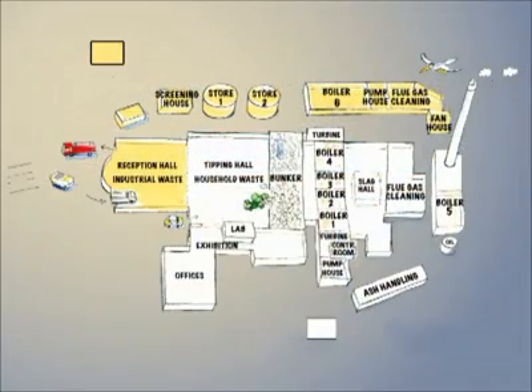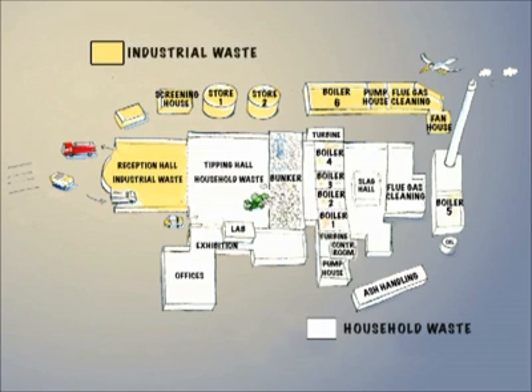The Högdalen Heat and Power Plant comprises two blocks, one for household waste and one for industrial waste. For household waste there are 4 grate-fired boilers with a total of 171 megawatts, and for industrial waste there is a 92 megawatt circulating fluidized bed. The machinery also includes state-of-the-art flue gas purification equipment, 2 steam turbines and an oil-fired boiler for peak load.